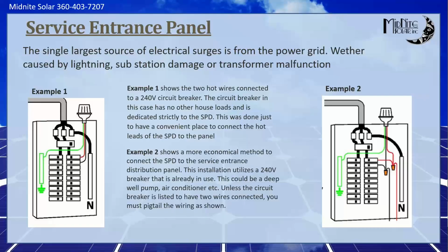Some breakers are listed for double wires under the breaker. You have to check that out. So in this example over here on the right, if the breaker was listed for 2 wires, you could put the 2 reds under one and the 2 blacks under the other instead of splicing them. So that's a couple ways you do it, but always start with the main panel. Most importantly, that is the one you put in. If that's the only one you can afford, that is where you're going to get, I'm going to say 75, 80% of your damage, maybe more, is always going to come in through that utility.